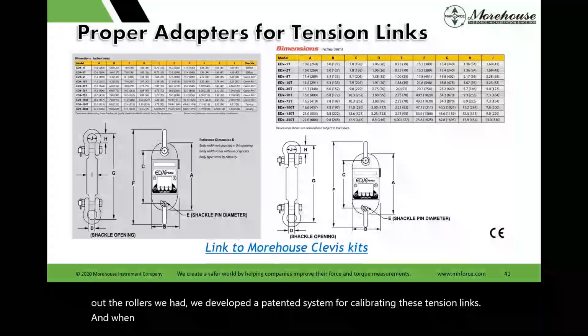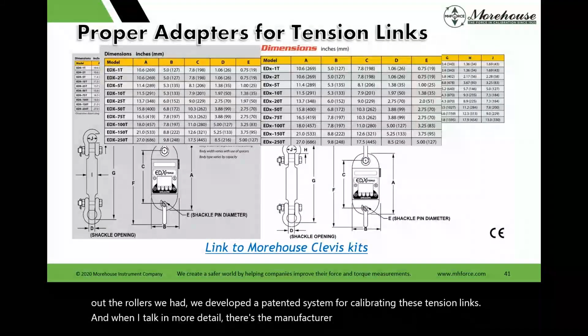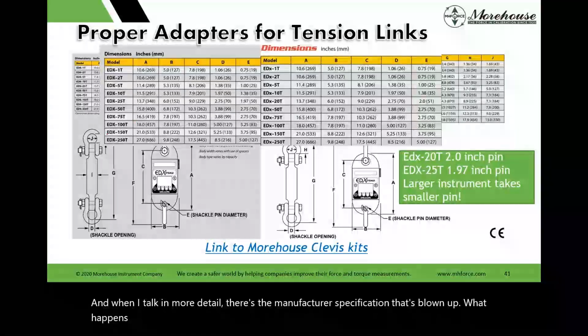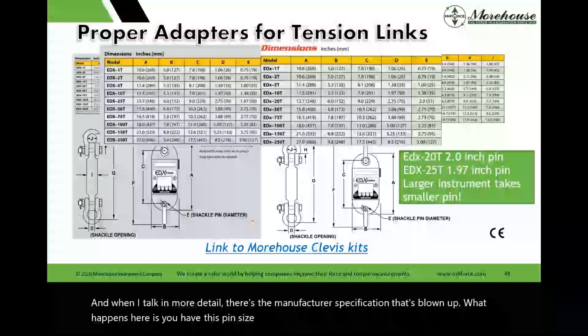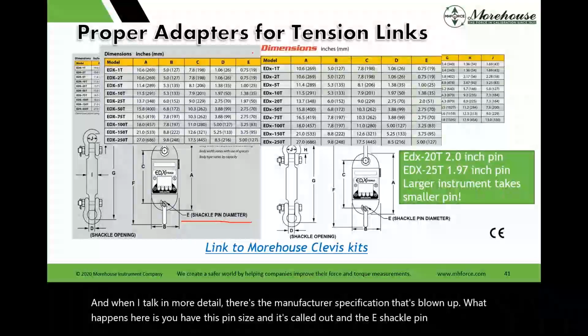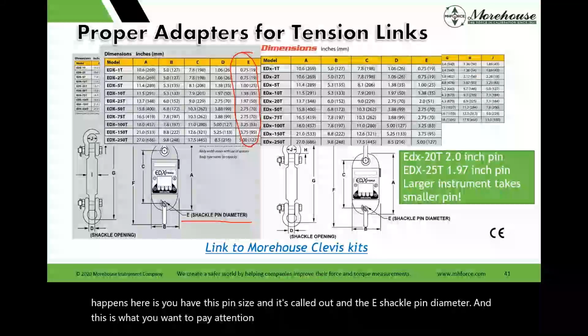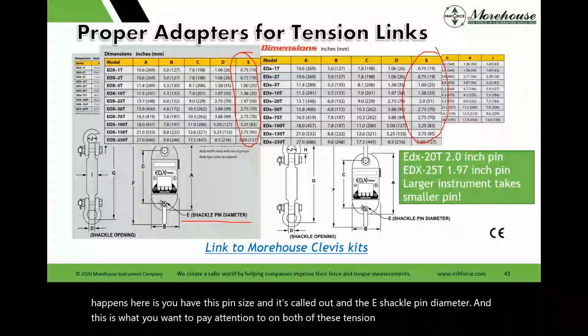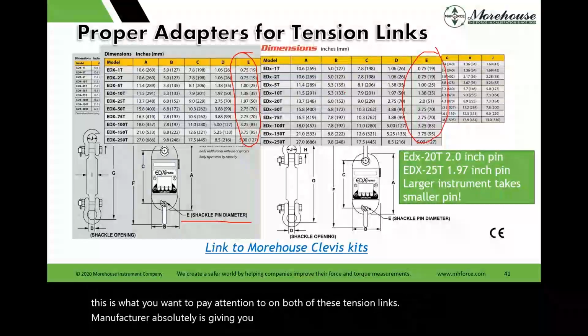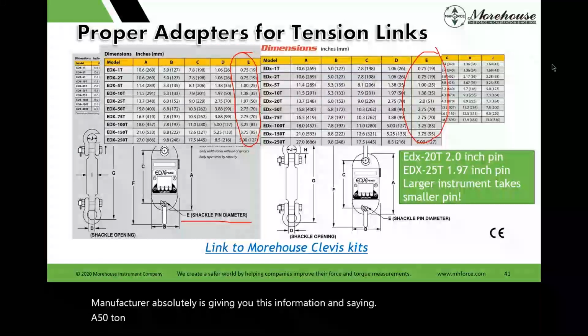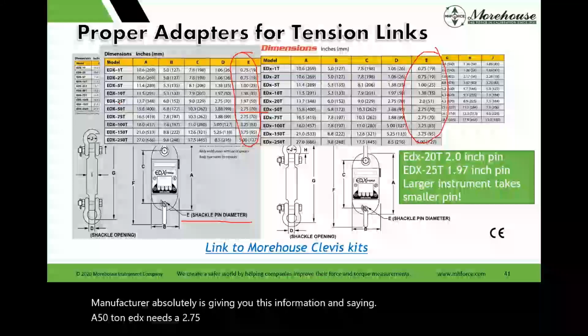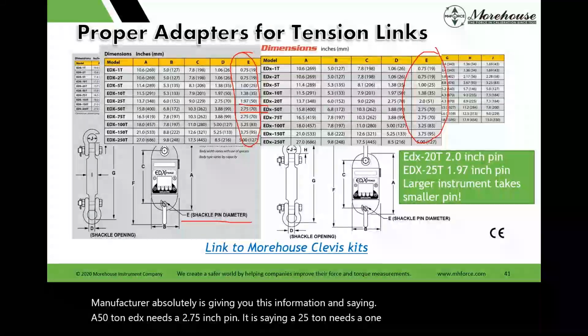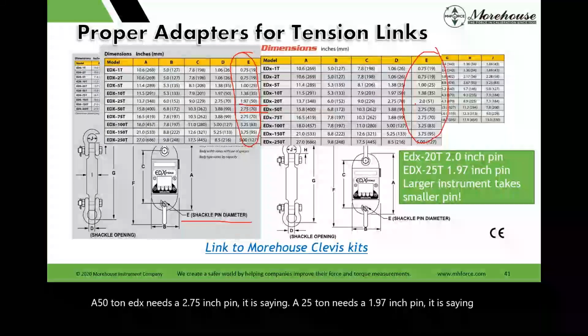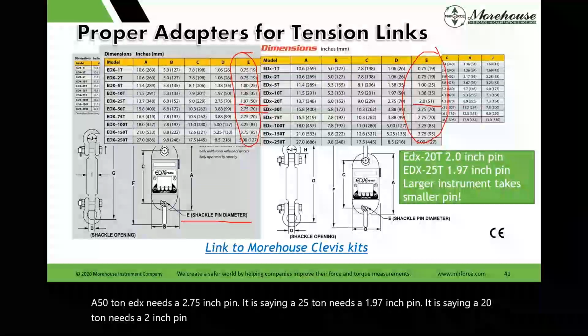And when I talk in more detail, there's the manufacturer's specification that's blown up. What happens here is you have this pin size, and it's called out as the E shackle pin diameter. And this is what you want to pay attention to on both of these tension links. The manufacturer is absolutely giving you this information, saying a 50-ton EDX needs a 2.75 inch pin. It is saying a 25 ton needs a 1.97 inch pin. It is saying a 20 ton needs a 2-inch pin. And yes, there is a difference between a 2-inch pin and a 1.97 inch pin.